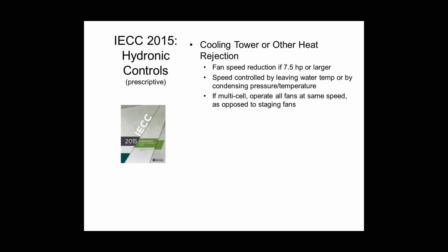If you have a multi-cell cooling tower, you need to operate all the fans at the same speed as opposed to staging the fans. So in other words, let's just say, keep it simple, you have two fans. Instead of running one at 0 and one at 100%, you would run two at 50% or whatever flow you needed, right? If you had 8 of them, same kind of thing, you'd run them all at some lower capacity, and then only if you get down below the minimum that you can run them at, then can you start staging them off. There are some exceptions on that one, I believe, that if the manufacturer has a specific recommendation, you could follow that instead of this. But for the most part, you're going to ramp the fans down together, which is smarter because you get more surface area per airflow, so you should want to do that anyway.